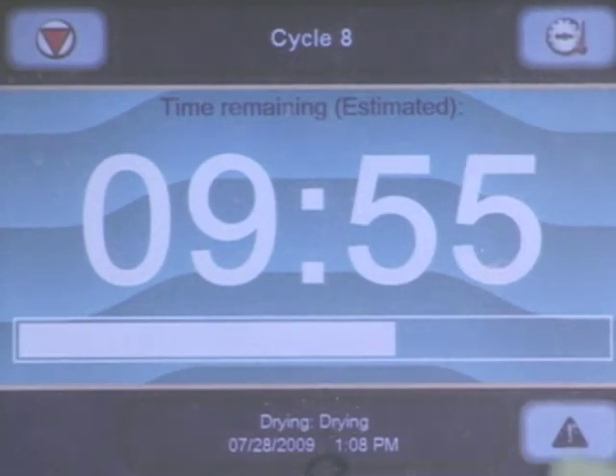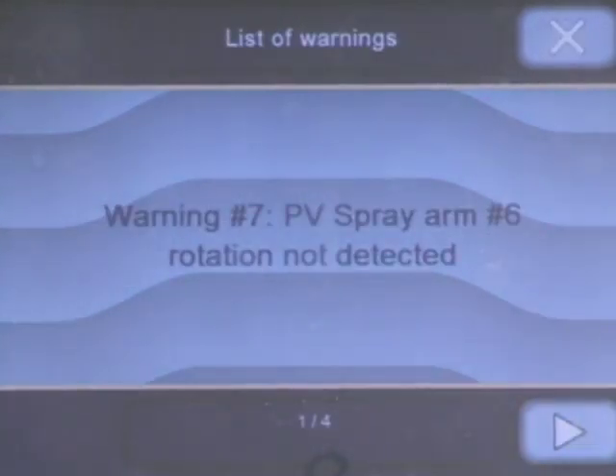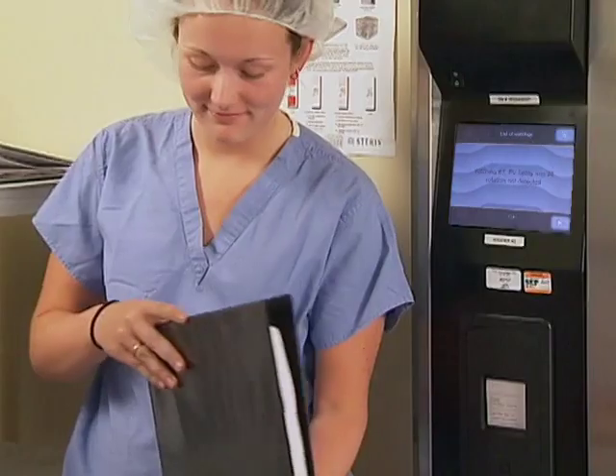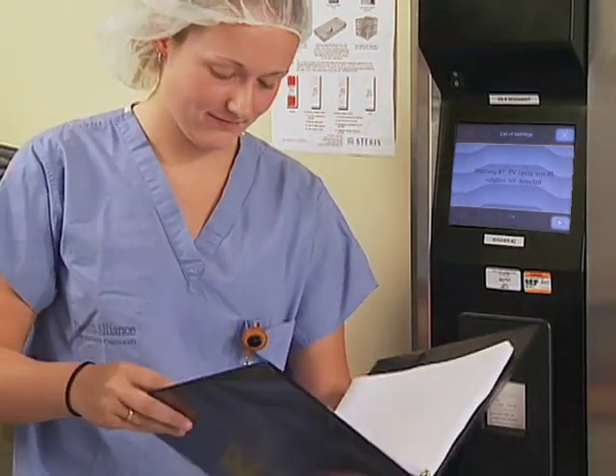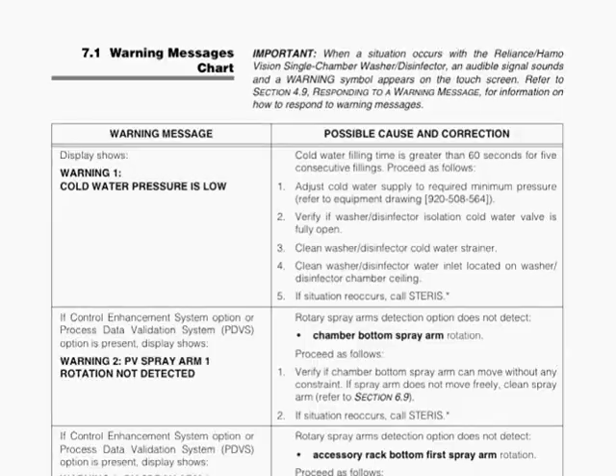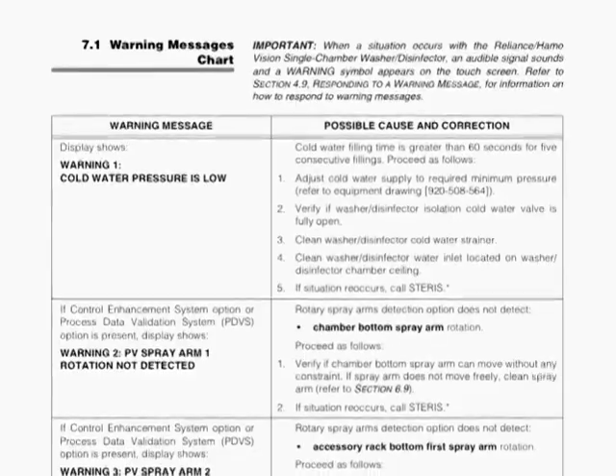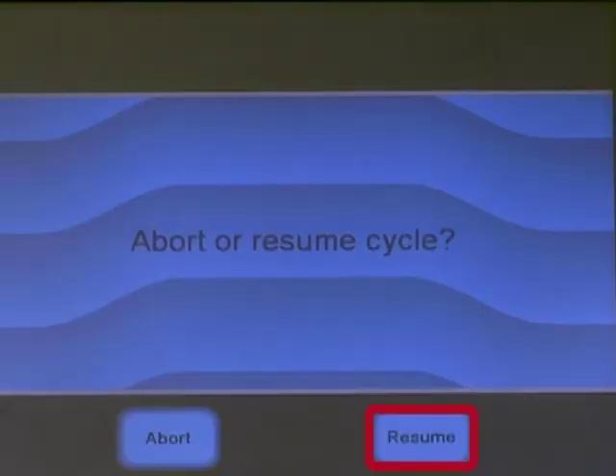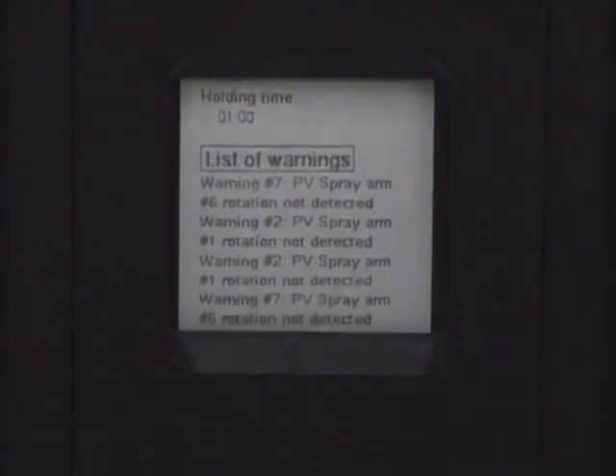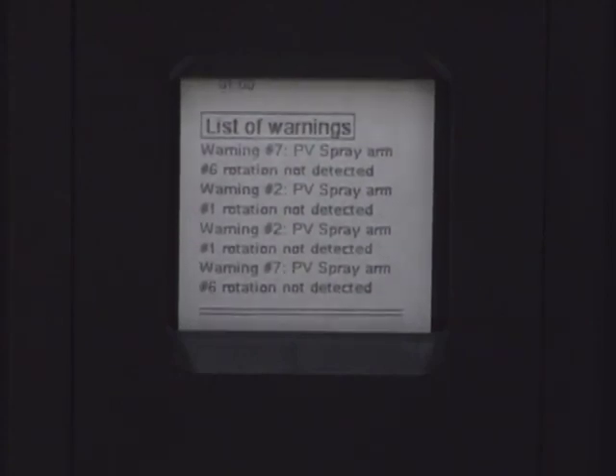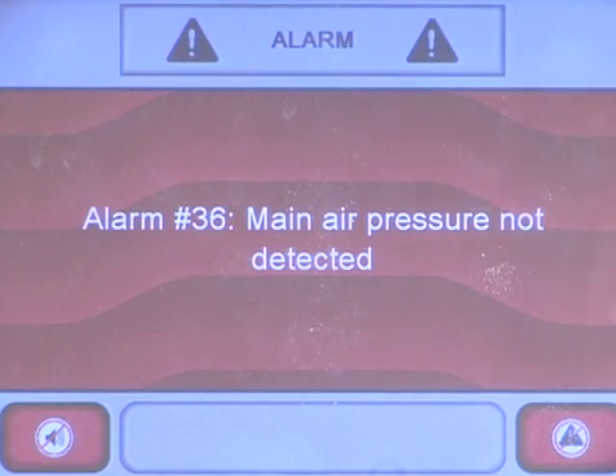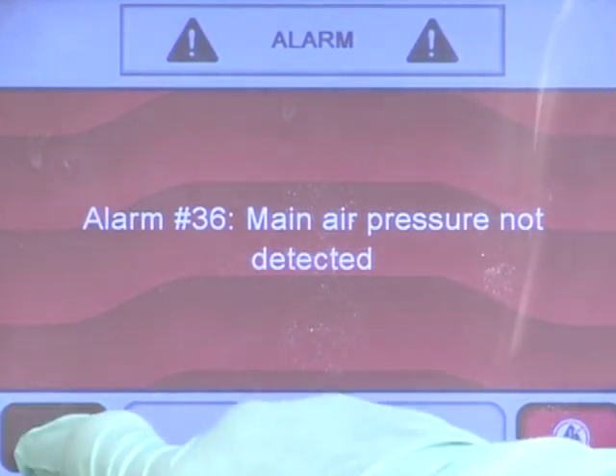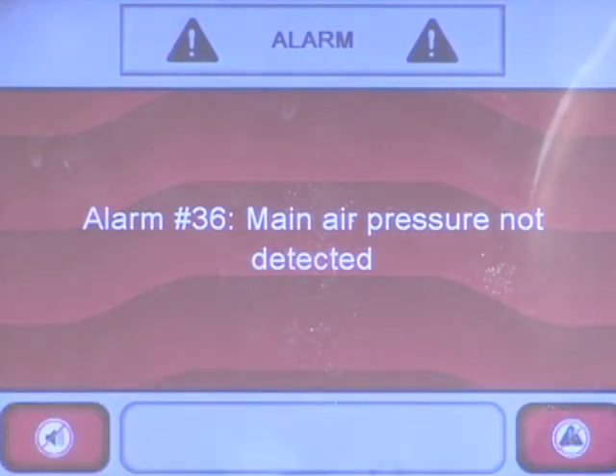If a warning occurs, press Warning on the control screen to review the details. To fix the issue, refer to the Warning Messages chart in Section 7 of your Vision single-chamber washer operator manual. Once the problem is resolved, resume the cycle. The warning will appear on the printout at the end of the cycle. If an alarm occurs, press the Alarm Ready button to acknowledge the alarm and silence the buzzer.